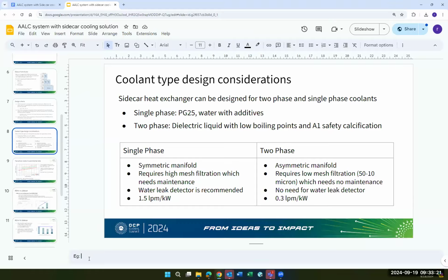I want to have at least some examples that are widely used, because there are no more Novec fluids coming, right? What are the fluids that exist in the market that can be used for this? That's something even I am curious about. Do you want it now, or do you want to add it later? I can give it to you now. It's R-1233zd.